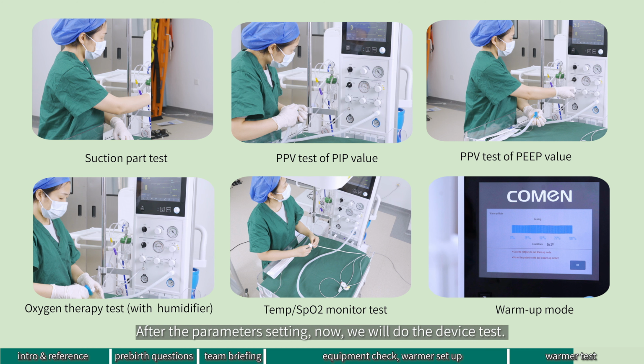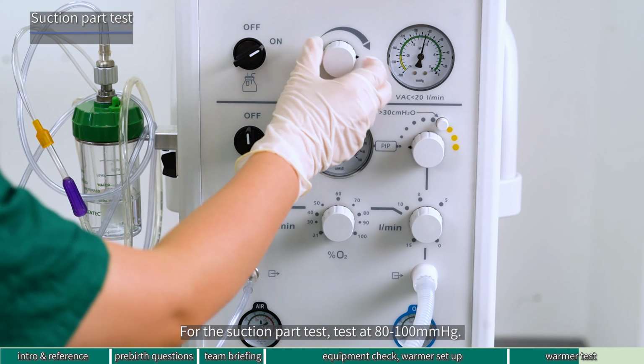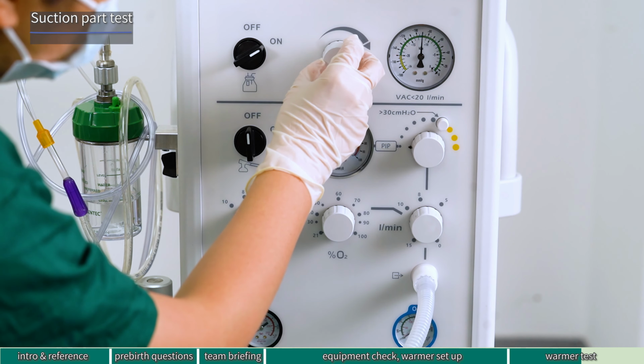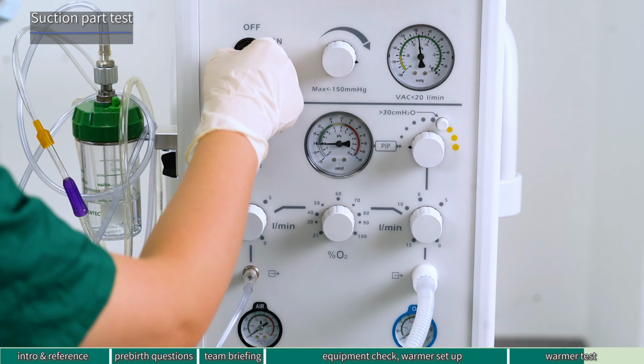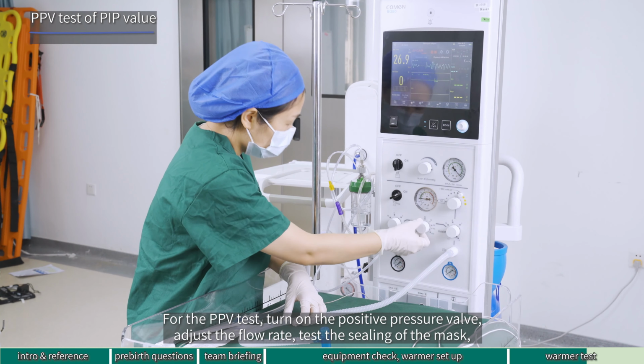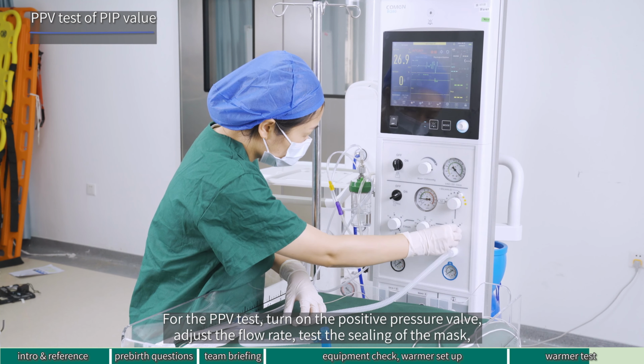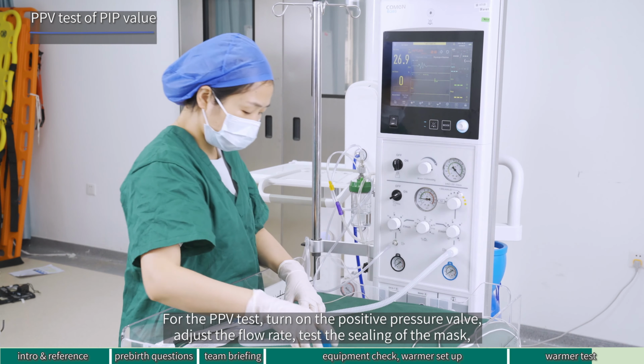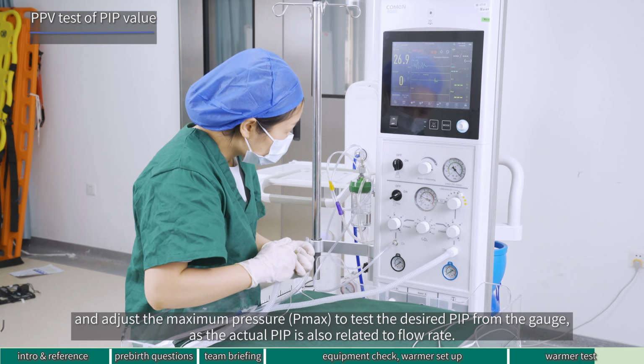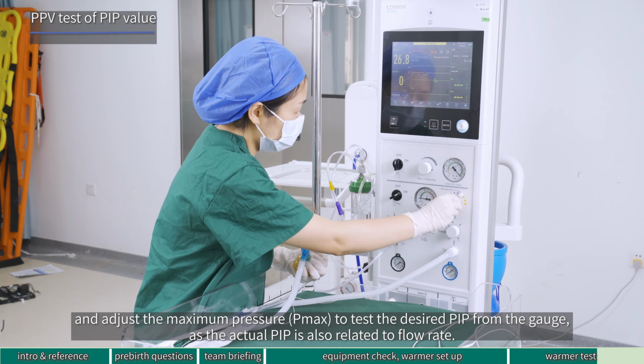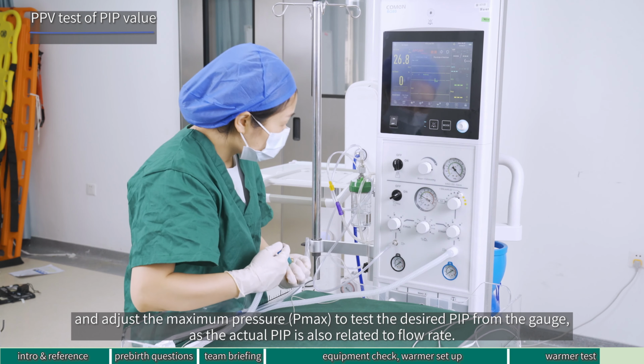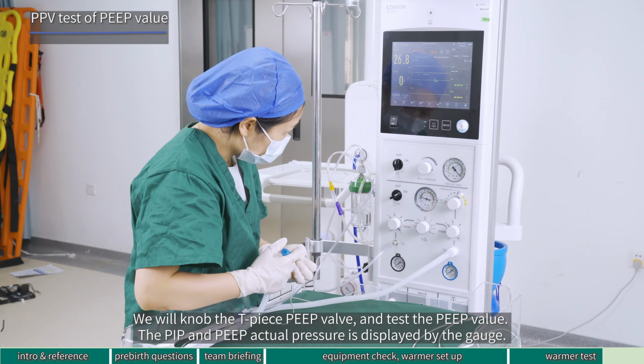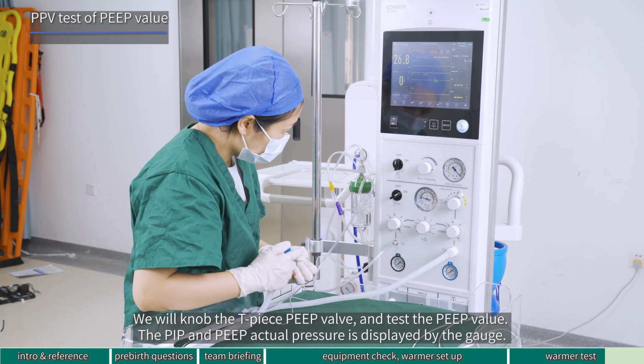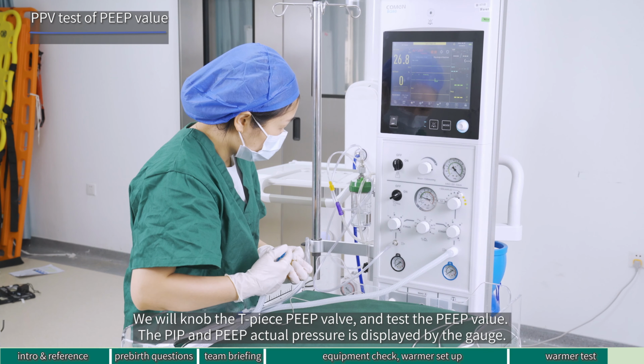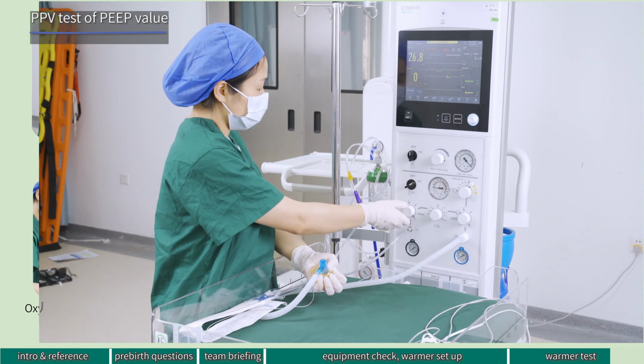After the parameters setting now, we will do the device test. For the suction part test, test at 80 to 100 millimeters of mercury. For the PPV test, turn on the positive pressure valve, adjust the flow rate, test the sealing of the mask, and adjust the maximum pressure, Pmax, to test the desired PIP from the gauge, as the actual PIP is also related to flow rate. We will knob the T-piece PEEP valve and test the PEEP value. The PIP and PEEP actual pressure is displayed by the gauge.